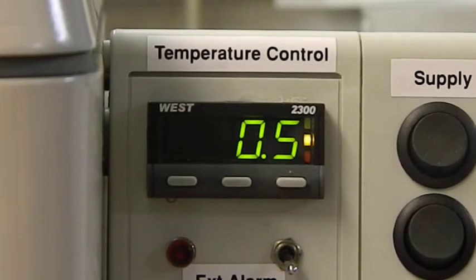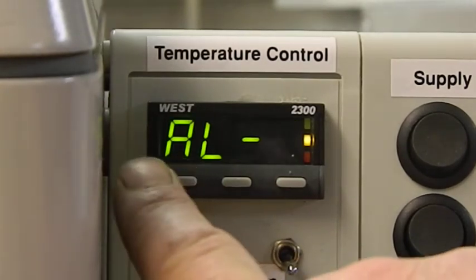AL1 minus. This is the amount in degrees centigrade that the alarm operates at. So if the machine, for some unknown reason, whether it's in a hot room or the sun's on it or whatever, goes half a degree over the set point, in this case 37.5, it will fire the alarms. And it will fire the alarms until it returns to the set point figure.